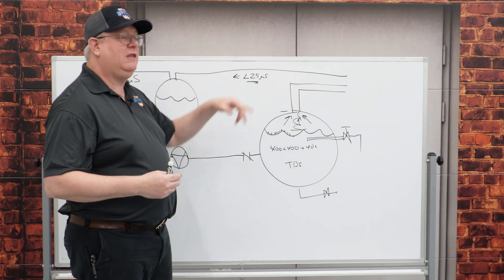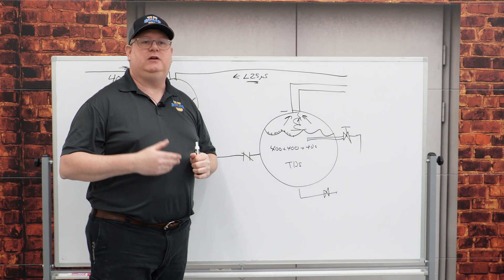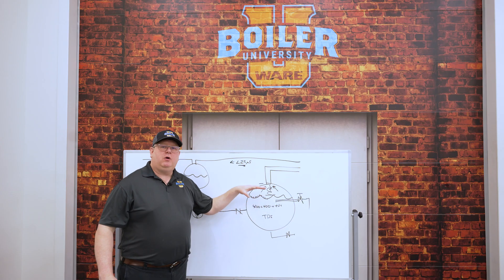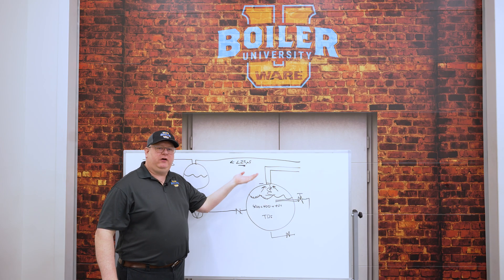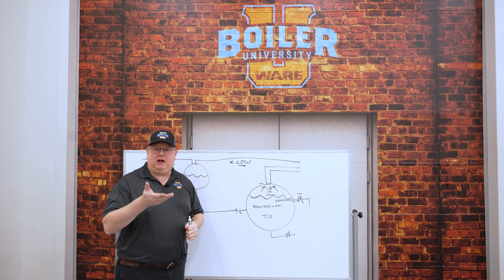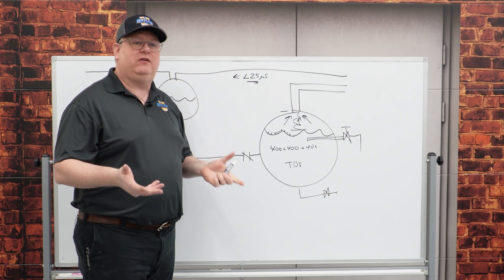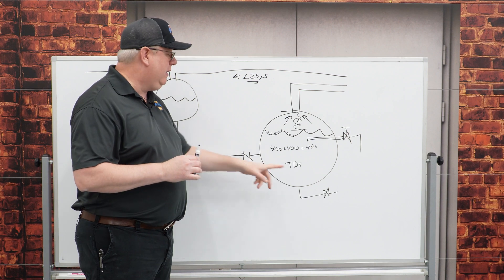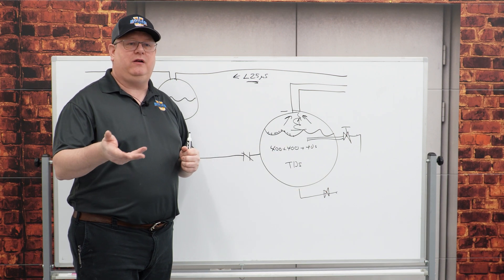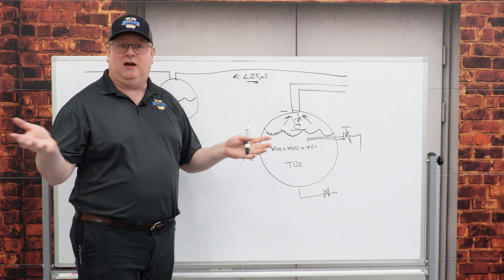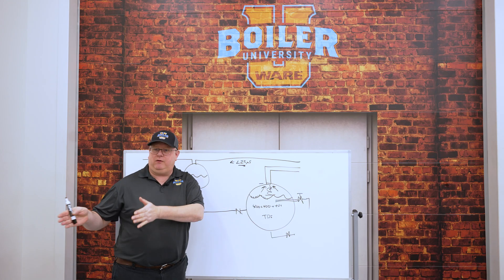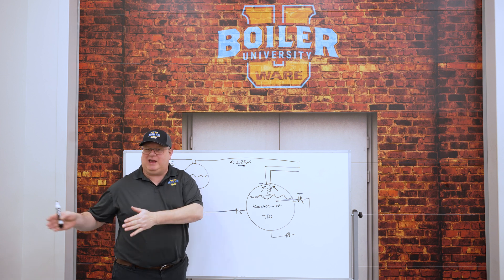So if you're monitoring that, check it during your highest load to make sure you're not getting carryover. If we detect carryover and our boiler water conductivity is high, we need to get rid of some of that water. One way we can do it is with a bottom blowdown, but the issue is that it's not something we can leave cracked unsupervised — we have to do the blowdown, then close it, and come back and do it again.